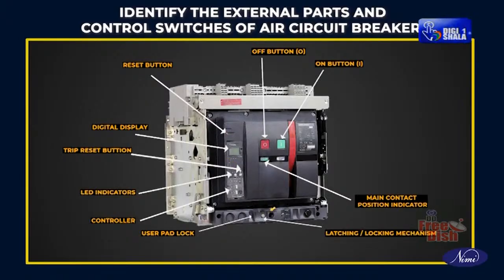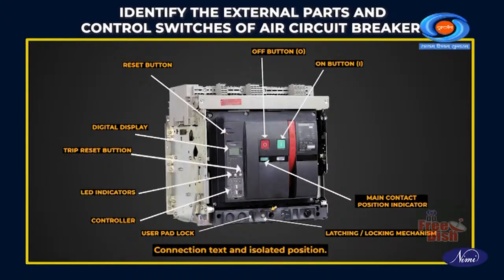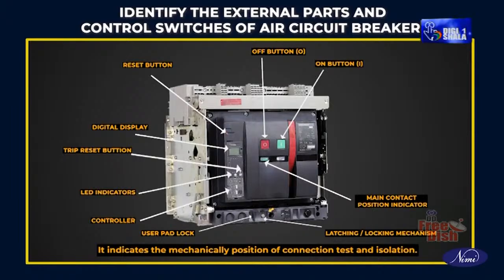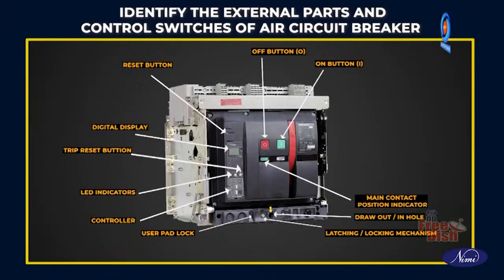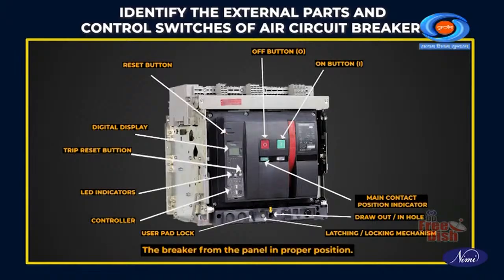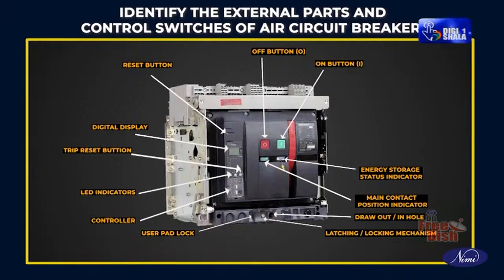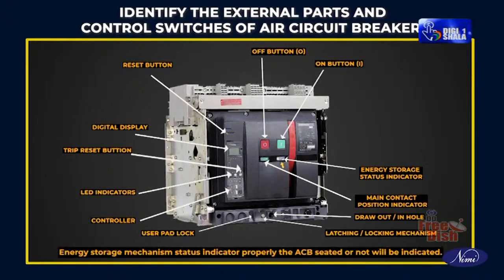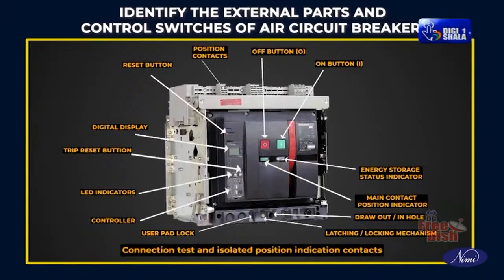Latching or locking mechanism: connection, test and isolated position. It indicates the mechanical position of connection, test and isolation. Draw out, draw in hole: for the breaker to the panel in proper position. Energy storage status indicator: energy storage mechanism status indicator. Whether the ACB is properly seated or not will be indicated.